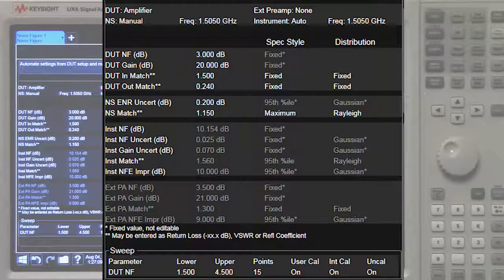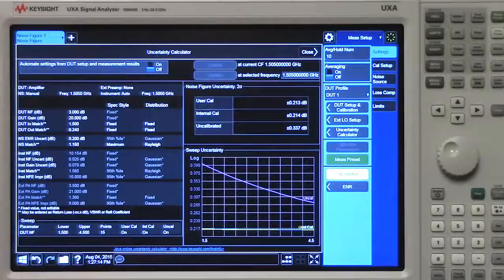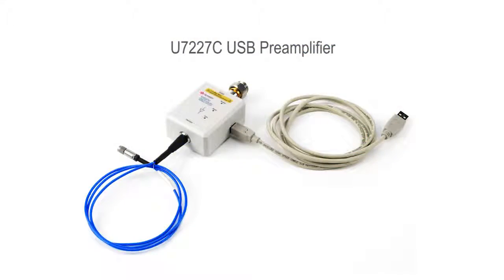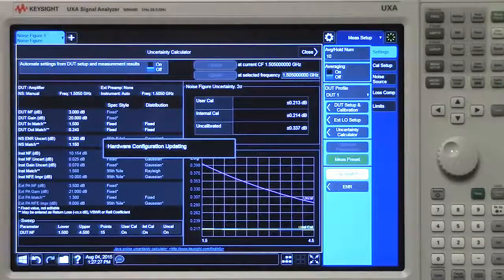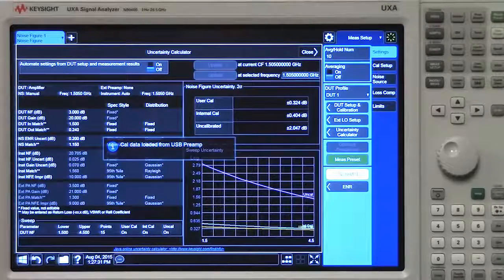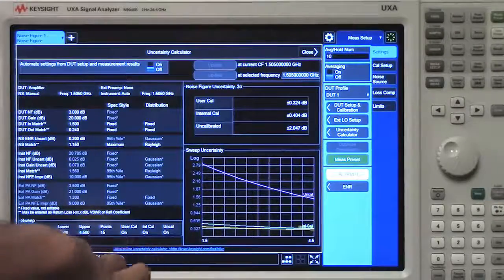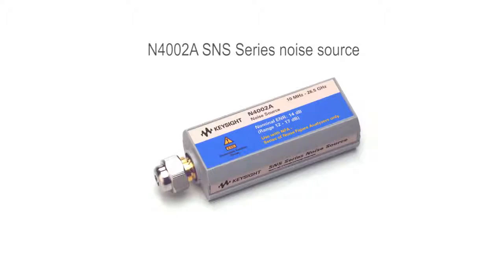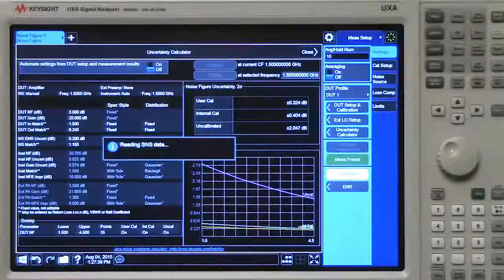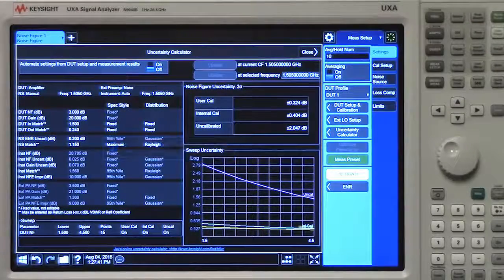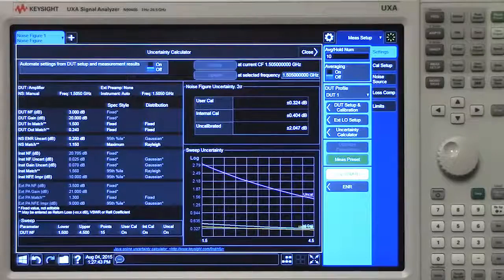Notice how the instrument populates its own noise figure, uncertainty, and other values. If I connect my external preamp right now, you will notice a splash screen pop up that says the hardware configuration is updating and cal data is loaded into the instrument. I'm also going to plug in the noise source right now, and another splash screen shows up saying that we are reading the SNS data to get the ENR values.